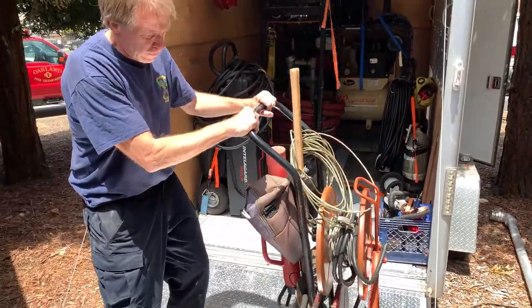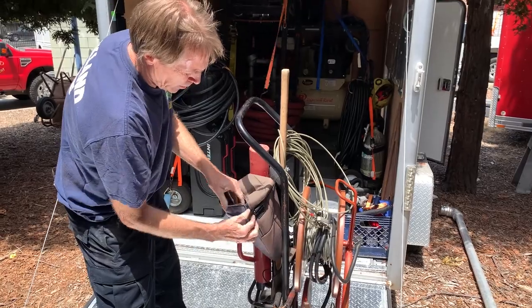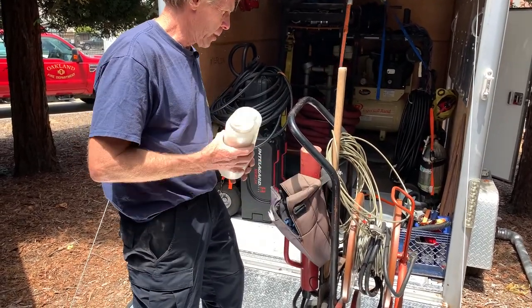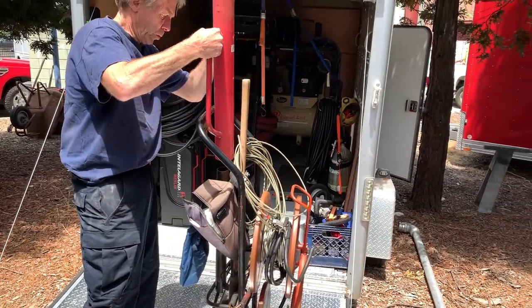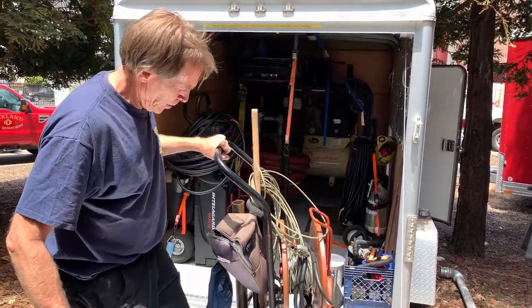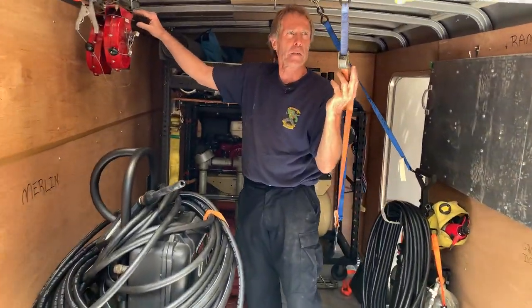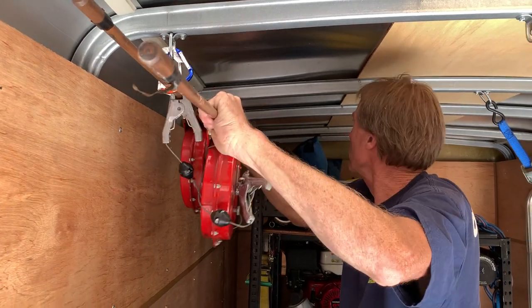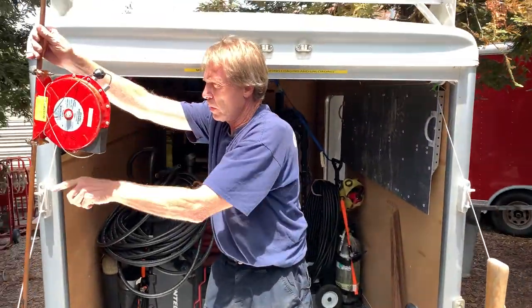This is quite a nice setup — we have two reels of grounding cable, a big jar of salt so we can wet a trench with sodium chloride if needed, and then lay a grounding rod in that trench. We also have a post hole driver for driving grounding rods into the ground, a little mini sledge for digging, and grounding rods in a couple of different sizes that come with the grounding cable already attached.